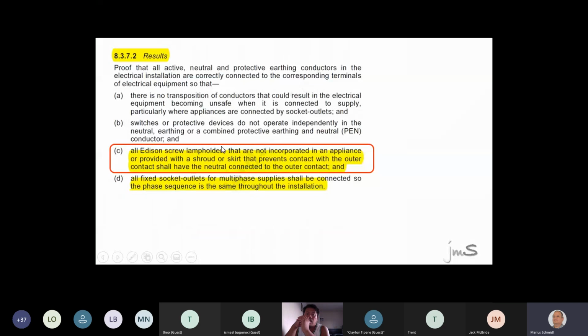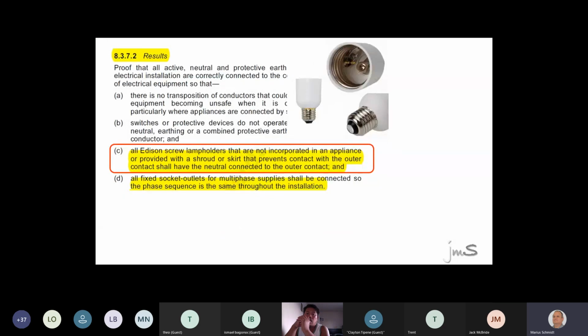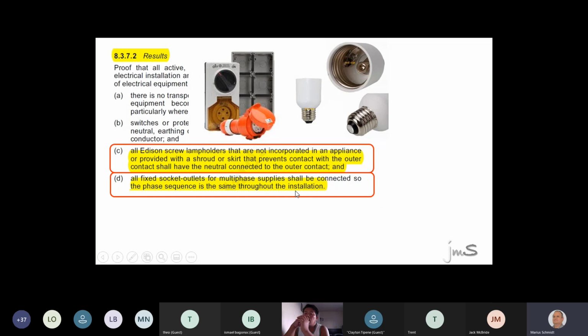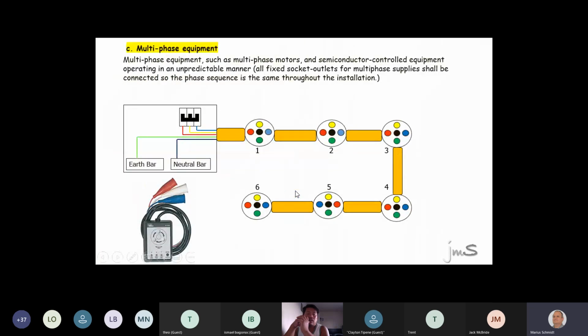Right, guys, a couple of things I want to ask. Have you guys ever heard about the Edison screw lamp holder? Do you all agree that the end over here is the phase and the side is called the neutral? Well done. Right, guys, have you ever heard about three-phase socket outlets? Right, we're going to do that now. It reads there, all fixed socket outlets for multi-phase supplies shall be connected so that the phase sequence is the same throughout the installation. Now, I've got a problem with that. Many moons ago, people never did it.